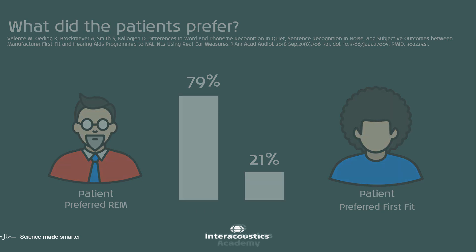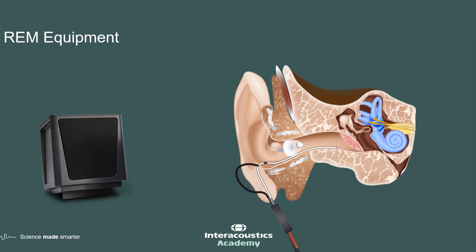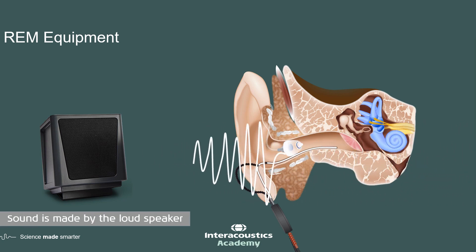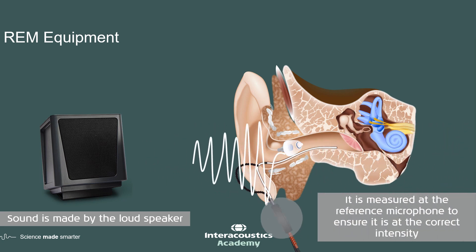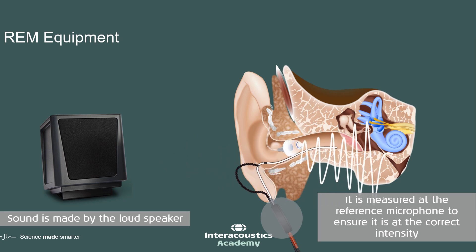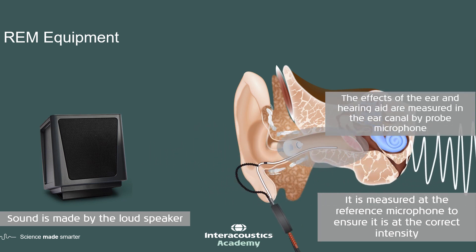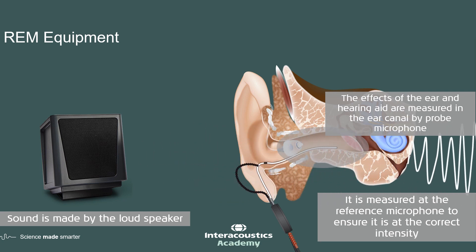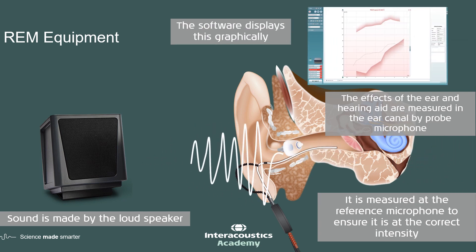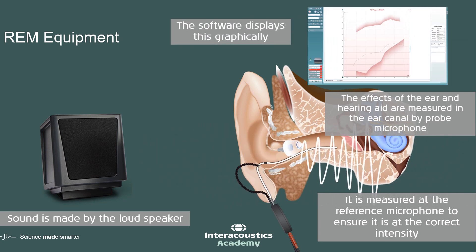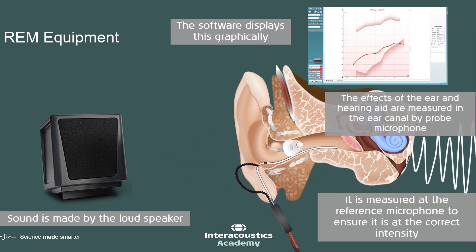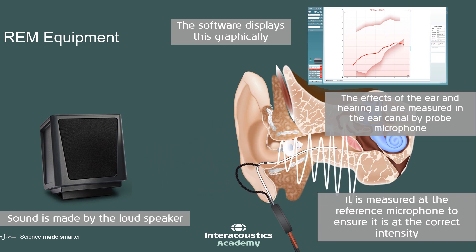So how do we actually perform real ear measurements? A simple diagram demonstrates how real ear measurement works and the equipment needed. The probe and hearing aid are placed into the ear canals, and a speaker plays a stimulus. The sound created by the loudspeaker is measured by a reference microphone, which ensures the sound is at the correct intensity. The effect of the ear and the hearing aid are measured by the ear canal probe microphone. The software then displays this result graphically so that the audiologist fitting the hearing aid knows how much to adjust the gain response of the hearing aid. This is a simplified schematic of the REM process.